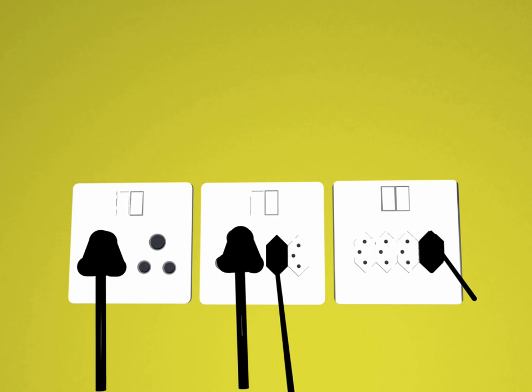The 3-pin version has a round protective earth pin of the same length and diameter as the line and neutral pins, but with no insulating sleeve. The protective earth pin's center is offset 3mm from the center point between the line and neutral pins.